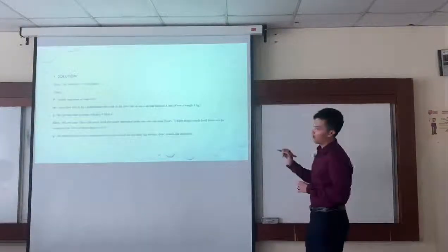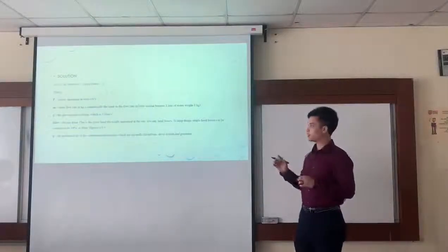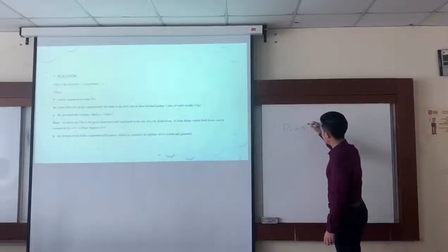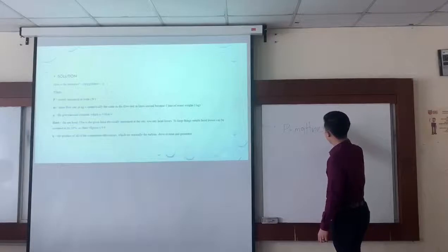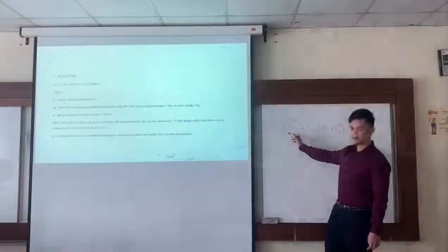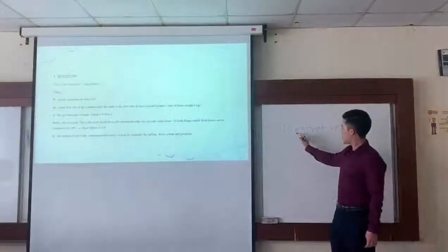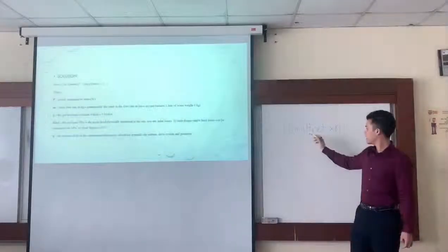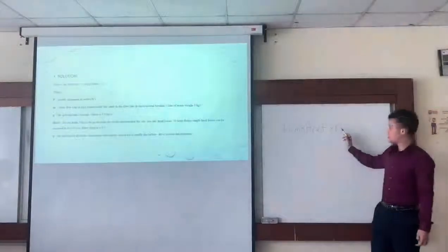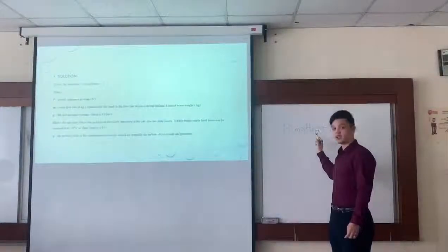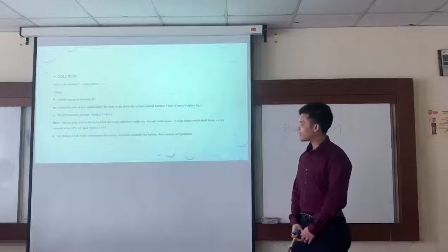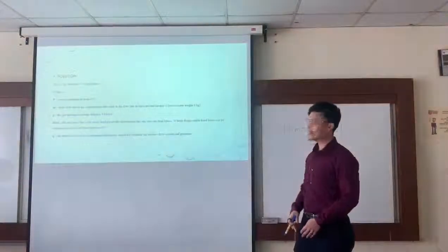First of all, the formula that is going to be used for this question is power P equals m g H net multiplied by the efficiency. We all know P is the power, M is the mass, G is the gravity, and these three are the basics. But the new ones are the H net and the efficiency. So I'm going to explain what the H net is. The H net is the net head. This is the gross head physically measured at the site, less any head losses.